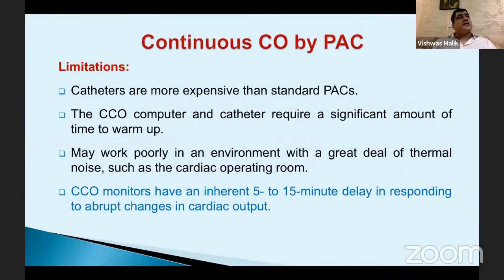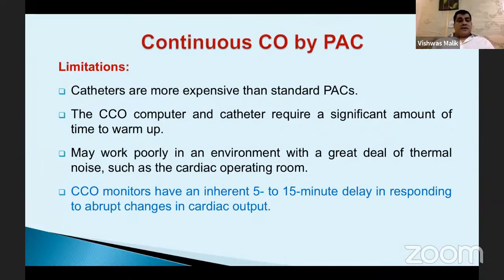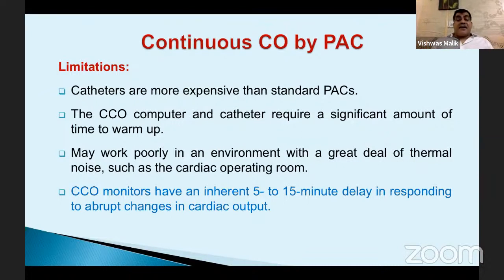However, CCO catheters are more expensive — approximately double the cost. The CCO computer and catheter require significant warm-up time and may work poorly in environments with too much thermal noise, such as cardiac operating rooms with cardiopulmonary bypass. CCO monitors have an inherent 5- to 15-minute delay in responding to abrupt changes in cardiac output, which is a significant limitation when rapid changes occur.